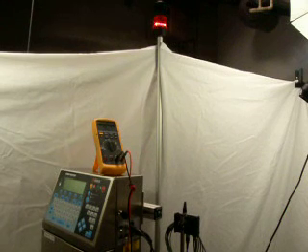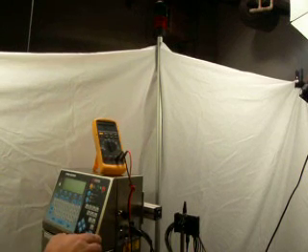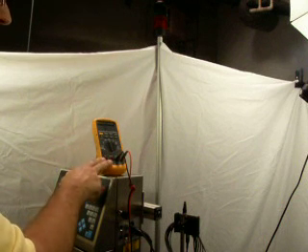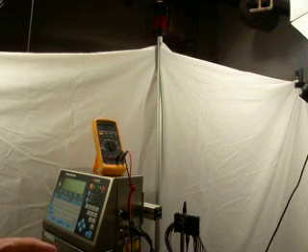Once the alert light changes to red, the buzzing you hear right now is actually from the 6200. I'm going to clear the alarm. And if you can hear also, there is no buzzing now coming from the meter, indicating our contacts have opened up and the conveyor will be stopped at this point.